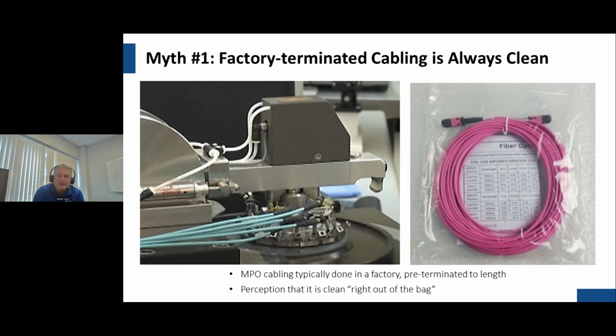Especially in the data center, we've seen some myths around why we don't need to do this. Probably the biggest one is the fact that within the white space, most of the cabling being deployed is pre-terminated cable. It comes with dust caps, or should come with dust caps, test reports in a nice plastic bag. The assumption is when you pull this thing out, put it in the containment, and snap it in place, it should be good to go - it should be pristine and there should be no issues around connector cleanliness.